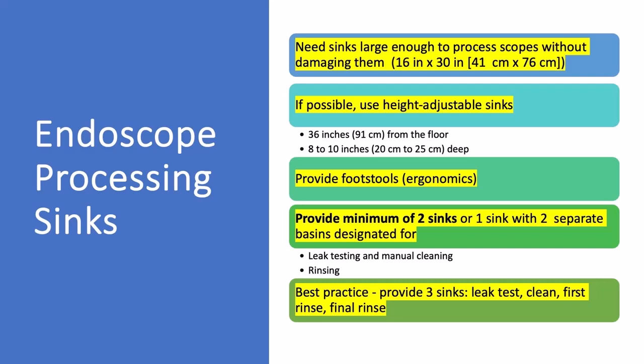You must provide, or should provide, a minimum of 2 sinks. In the first sink, you will do the leak testing and the cleaning, and the separate sink for rinsing and final rinsing. The best practice, though, is to provide 3 sinks: the leak test and clean in the first, rinse in the second, and the final rinse in the third.